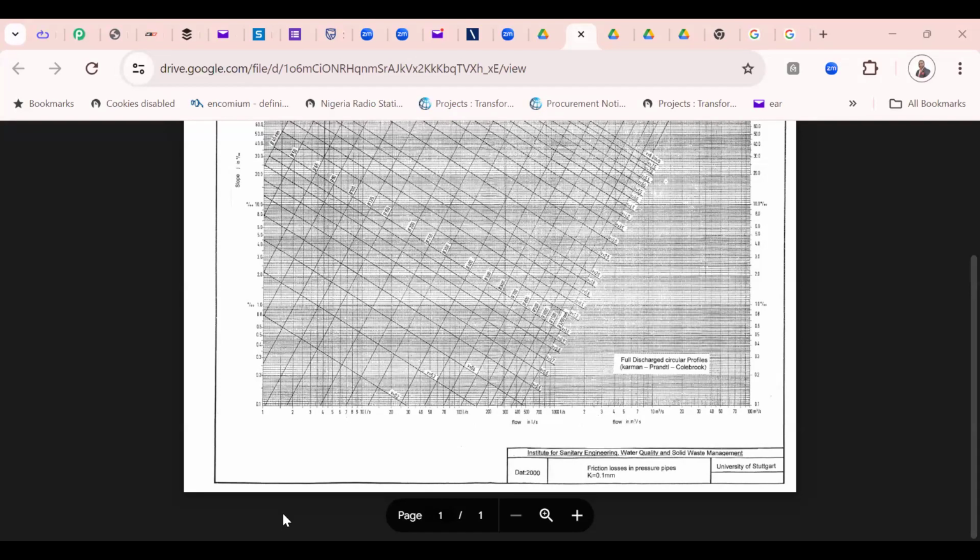I know people will have that challenge. That's why I threw the question. Before we leave the chat, I have a question. Let's now trace the velocity of flow. After checking the pipe size, I now trace the velocity of flow, and I'm having about 2.5 to 2.7 meters per second. Is that a good one for that run? No, but we're just making an assumption. We don't know. This is like real life.